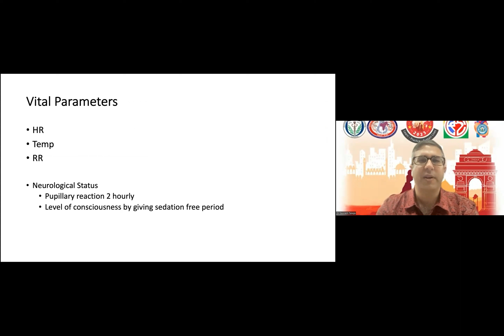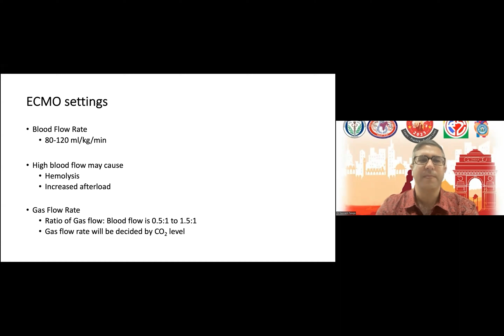as soon as the patient is stable. Now about ECMO settings, the blood flow rate can vary from 80 to 120 or 150, and high blood flow may cause hemolysis or increased afterload. The gas flow rate ideally is kept around 1 is to 1, but usually the range is 0.5 to 1.5 is to 1. And this gas flow rate will be decided by the carbon dioxide level that we want to keep. Now, settings of the heater cooler unit should be checked hourly, and we should adjust the temperature.